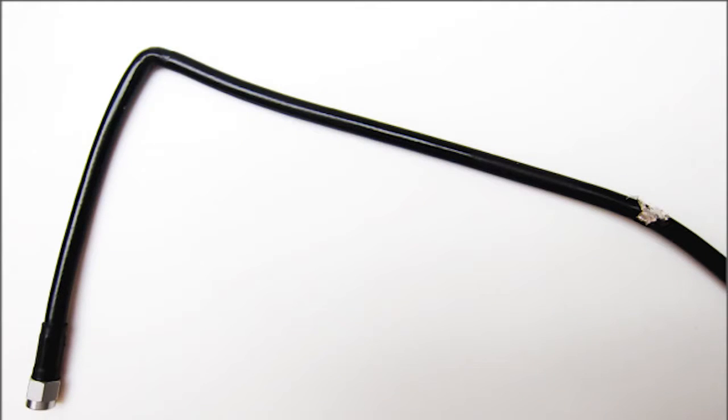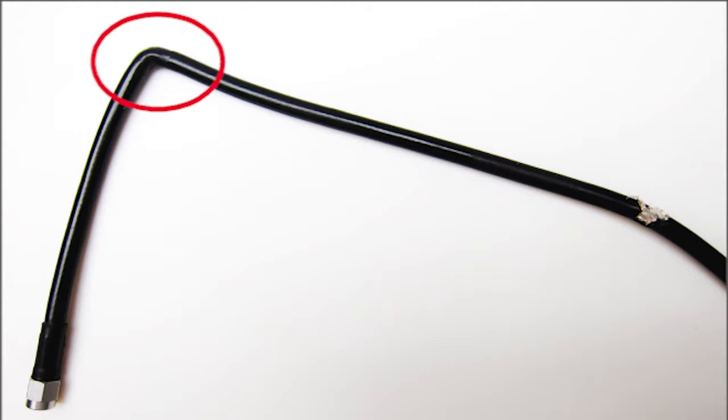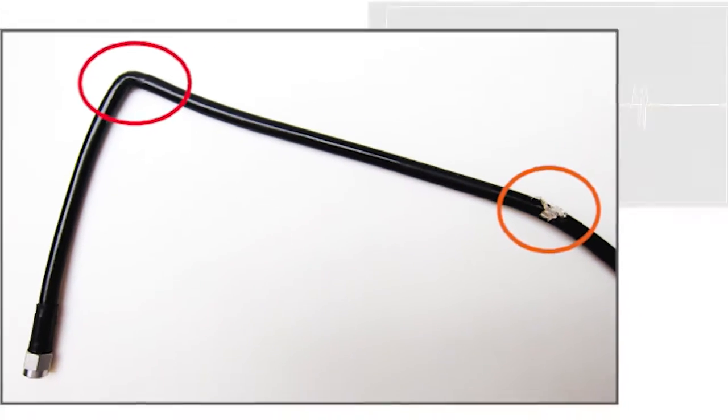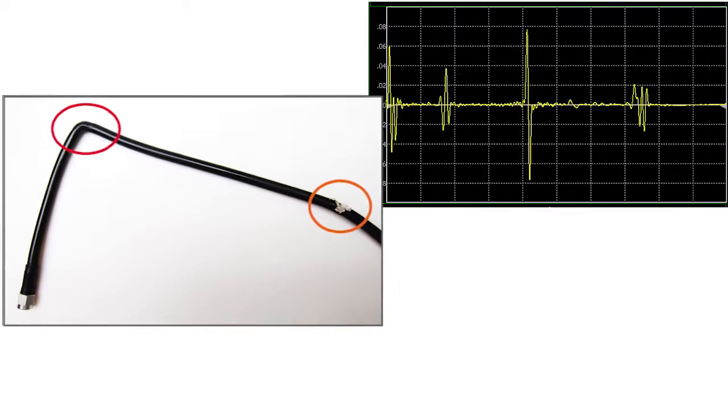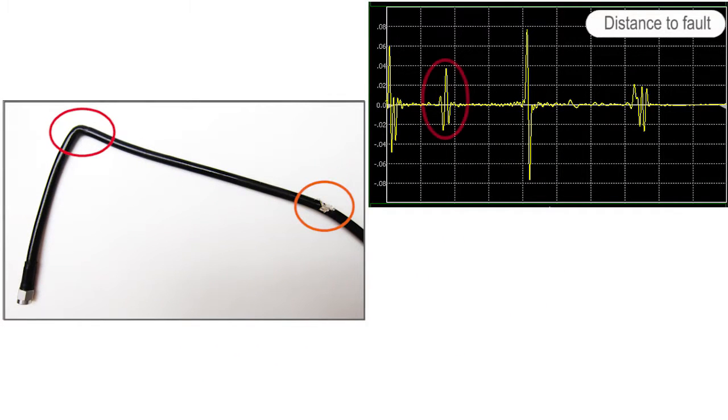In the case shown here, we have a damaged cable with bend radius exceeding specification and a nick in the outer shielding and dielectric.